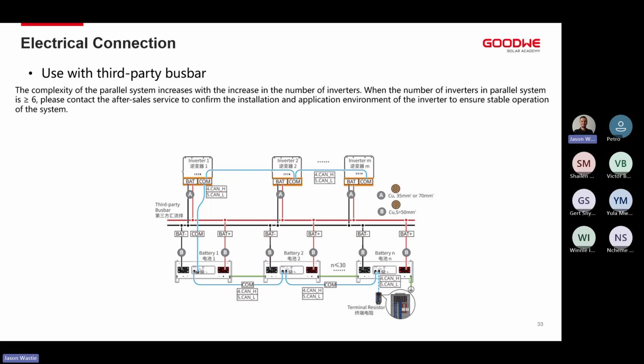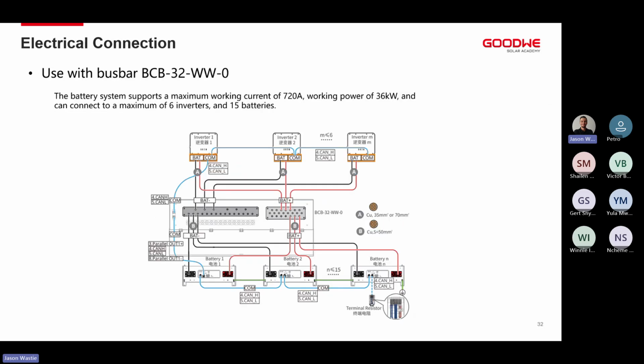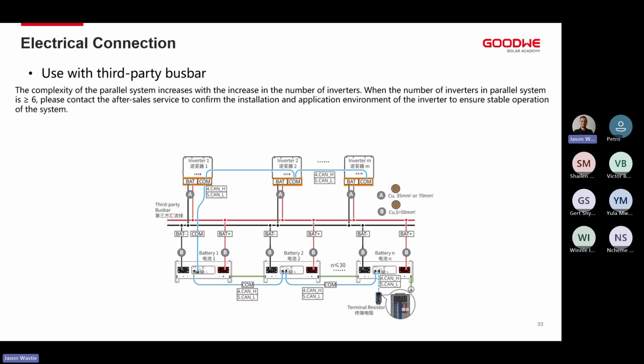You'll see the terminal resistor in this battery pack as well, slightly different to one of the previous ones. Inside the box with the battery, you'll get 2 terminal resistors. One is white and one is black. Please keep both of them with you just in case, and make sure to reference the manual as to which one you need. This one terminates 7 and 8, this one terminates 6 and 8. They terminate the different cables depending on the communication that you're using.